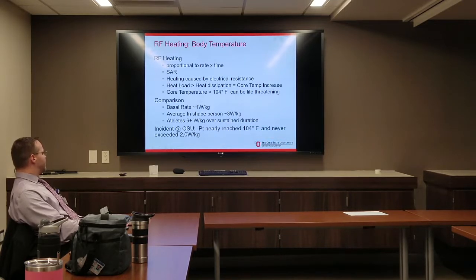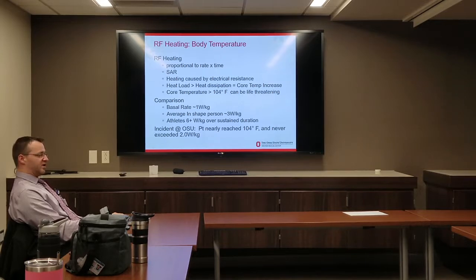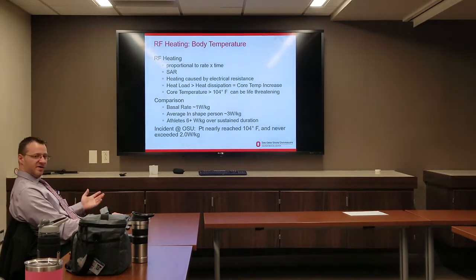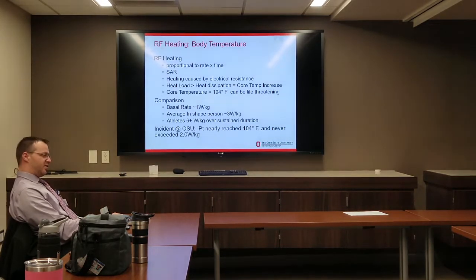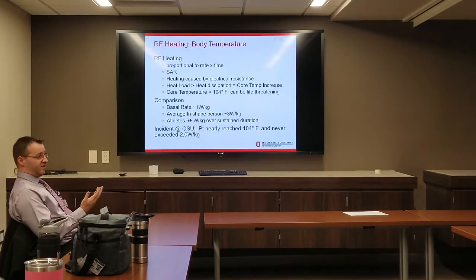For comparison: most people at a basal rate can easily handle and dissipate 1 W/kg. An in-shape person can dissipate up to about 3 W/kg without much trouble. Athletes can easily dissipate 6 or more W/kg for sustained duration. If you have very unhealthy or obese patients, you'll need to be more concerned about RF exposure and may want to stay in normal operating mode, questioning whether first level mode is absolutely necessary.